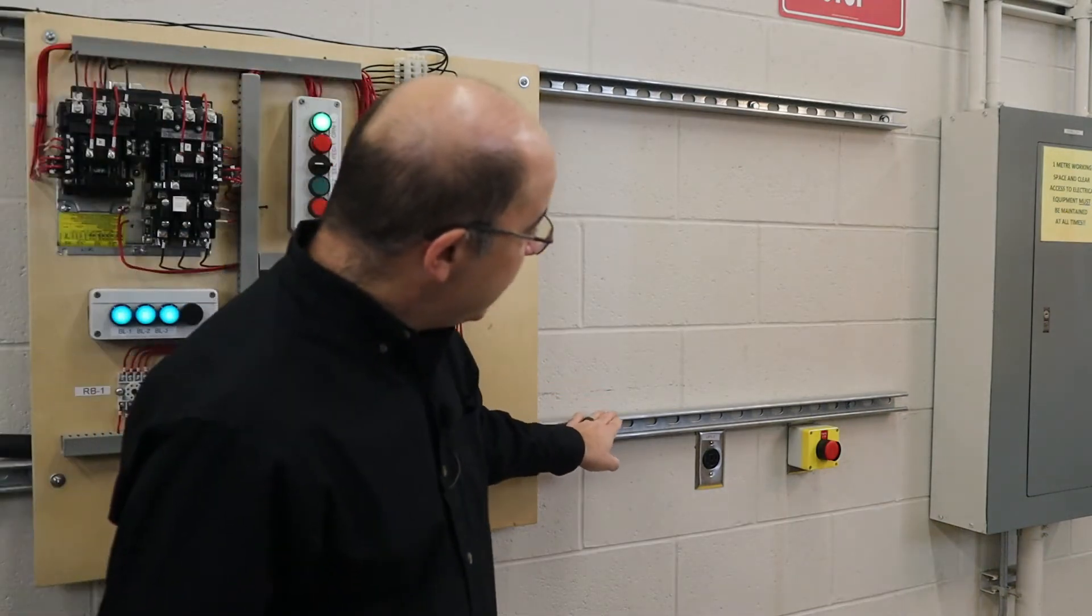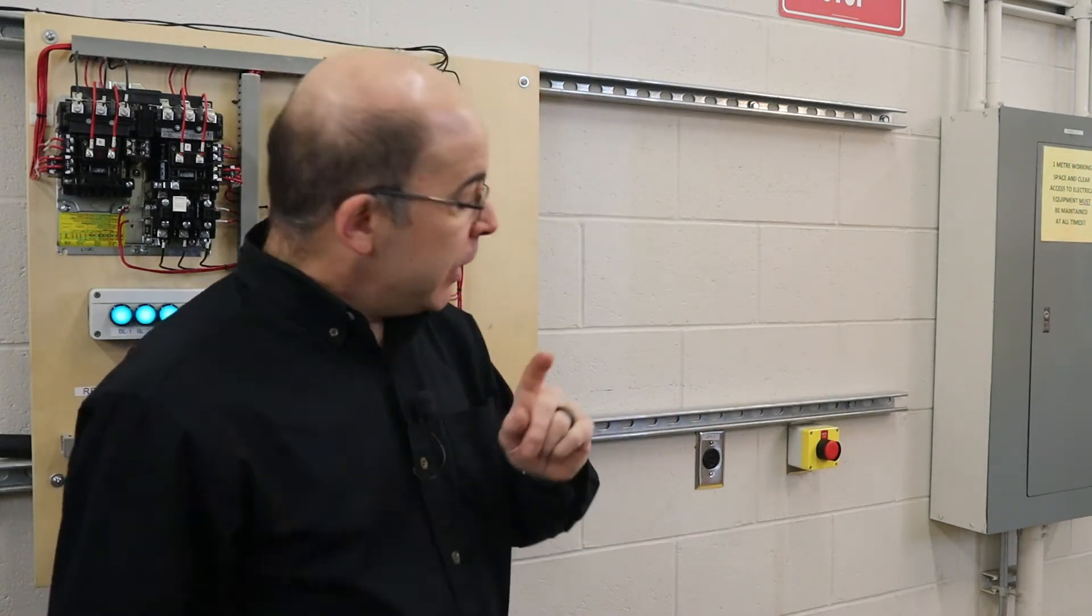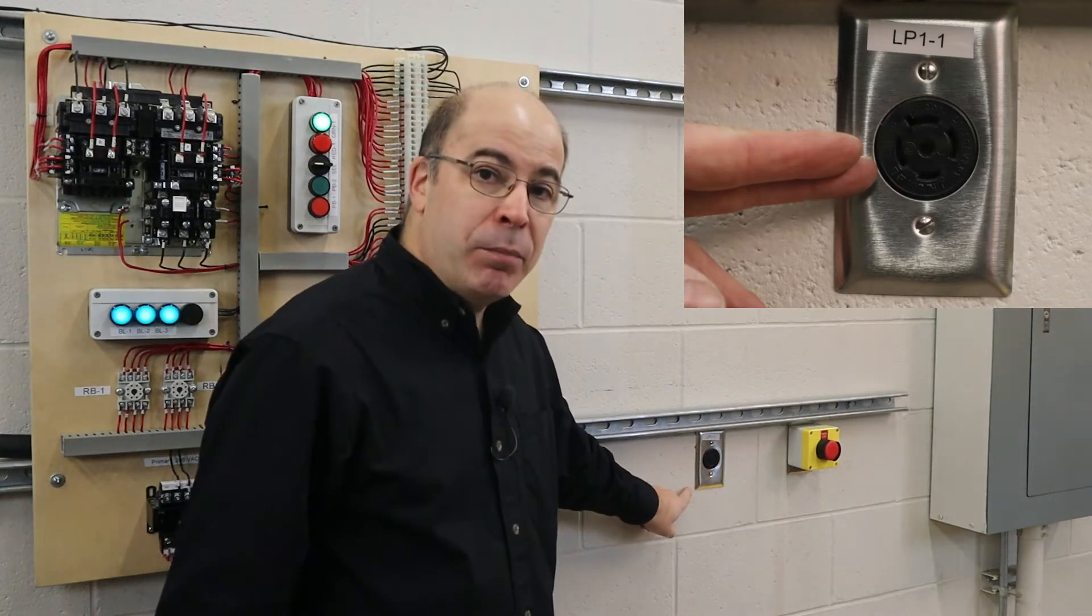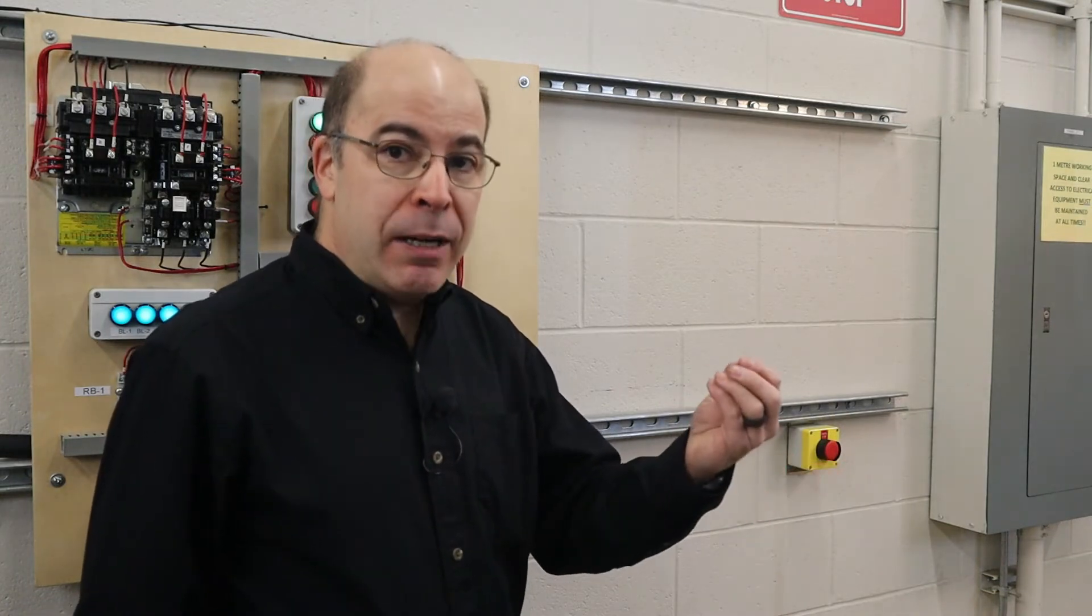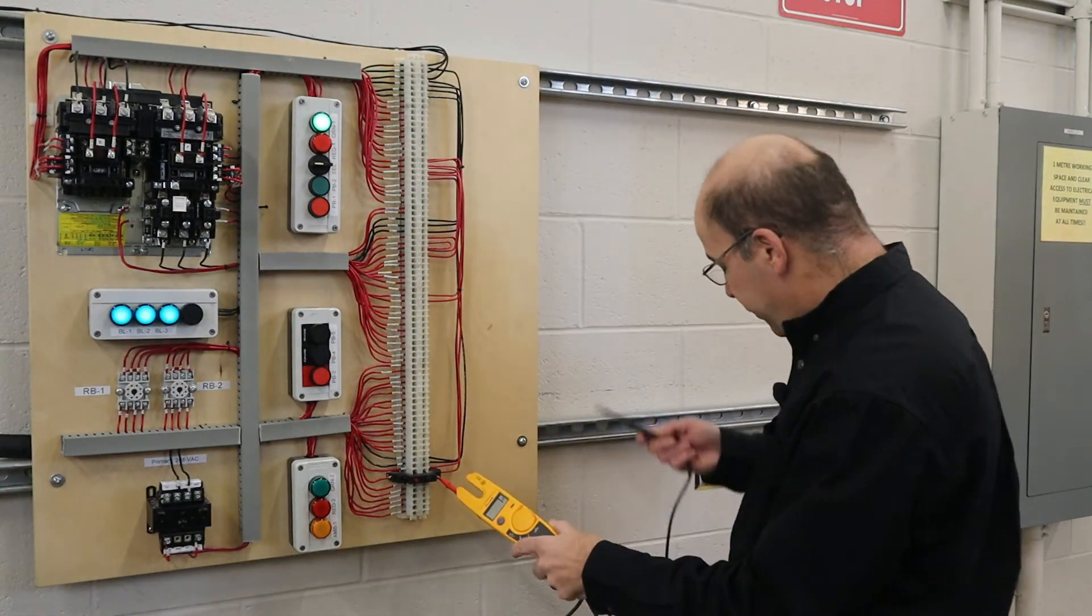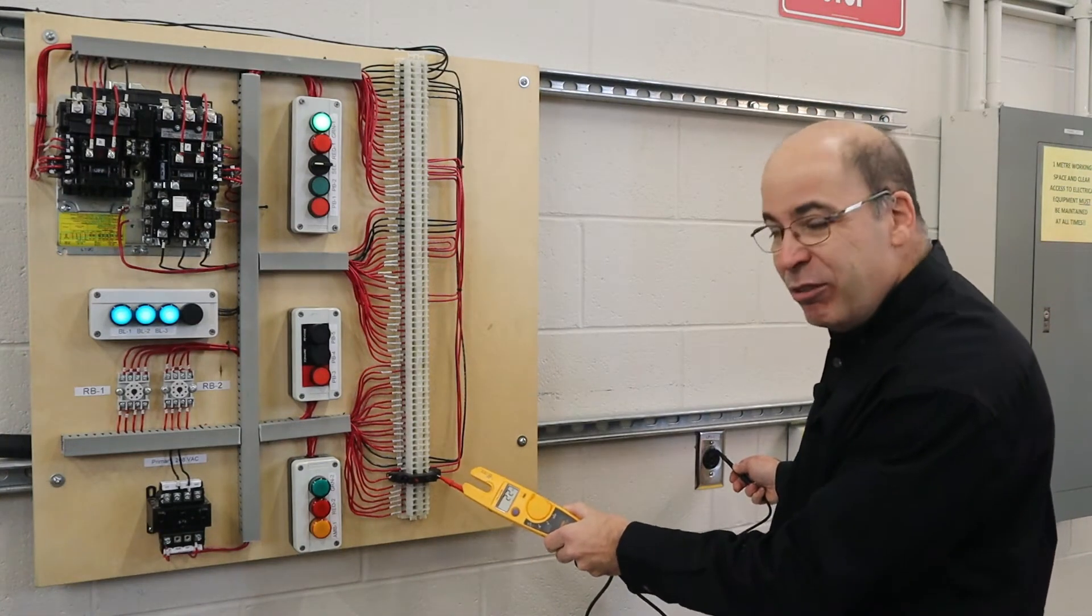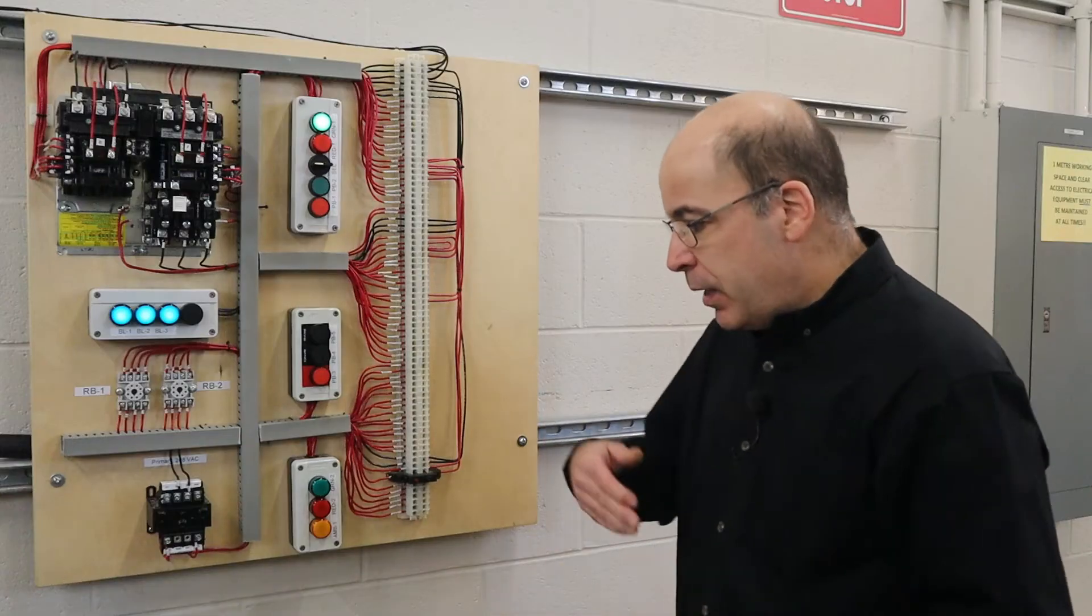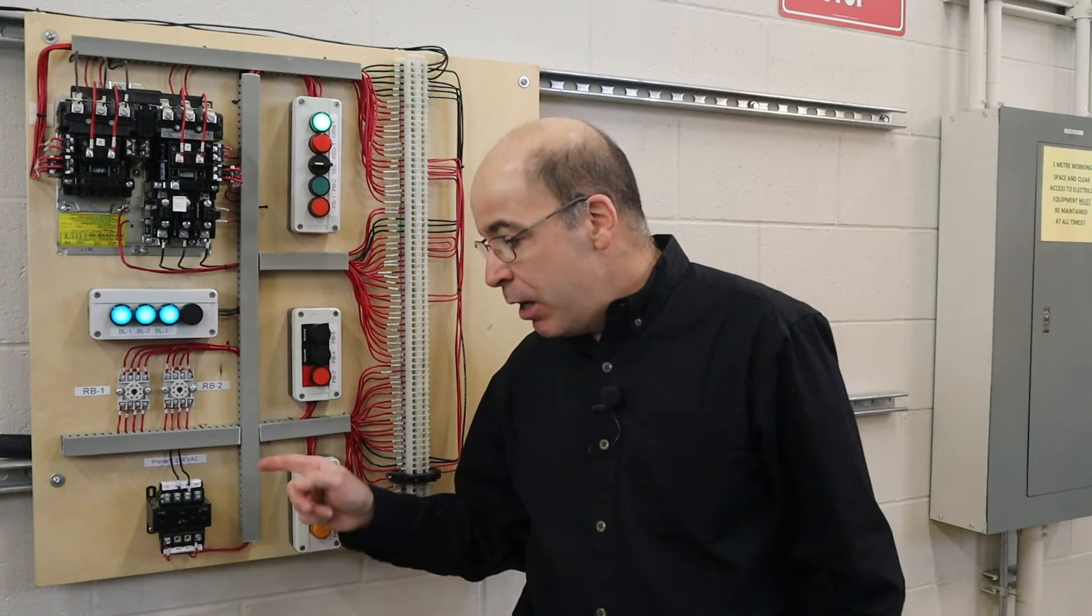Now when we look at this bar, we can see that is just a steel bar that is bolted to a concrete wall. It's not bonded anywhere, but it would be reasonable to expect that the faceplate of this receptacle and even the center pin is grounded. As an electrician, I know that. So let's try and take a reading to what we know is a bond or a ground point. So if we take the meter and I go right to the cover plate, which is steel—it's stainless steel but it still counts—I still get 22 volts. This is my main point. We have an unbonded or a floating neutral on the secondary side of this transformer.